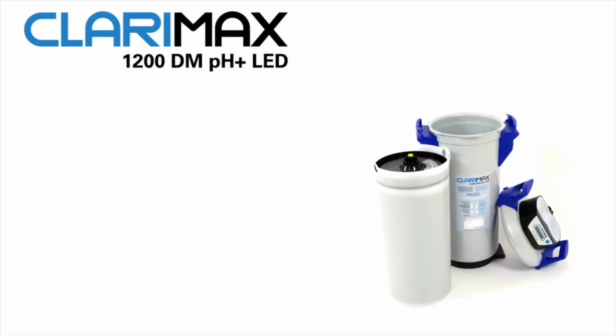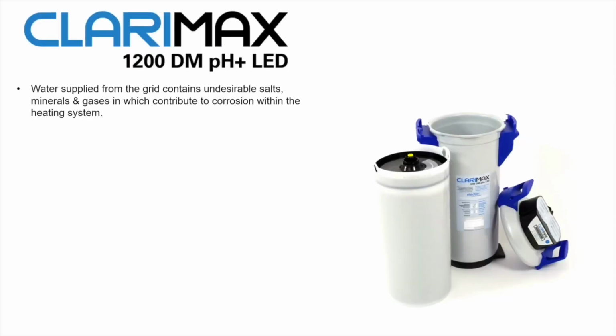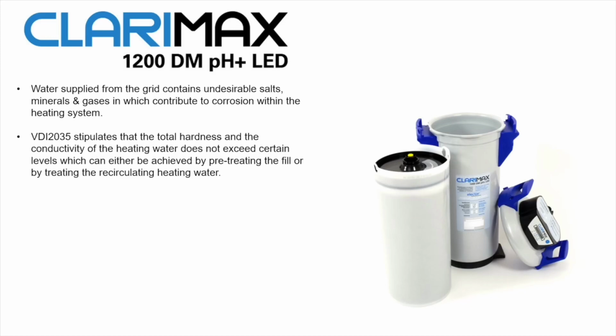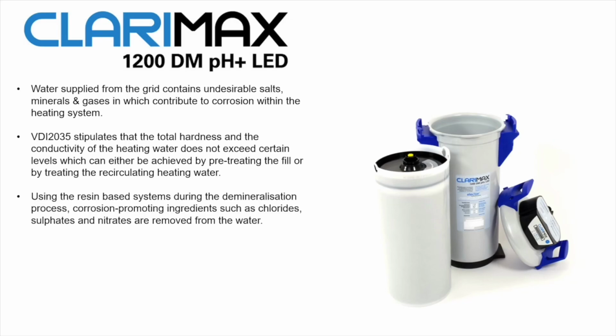Quick look at the Clarimax here. Water supplied from the grid contains undesirable salts, minerals and gases which contribute to corrosion within the heating system. VDI2035 stipulates that the total hardness and the conductivity of the heating water does not exceed certain levels, which can either be achieved by pre-treating the fill or by treating the recirculating heating water.